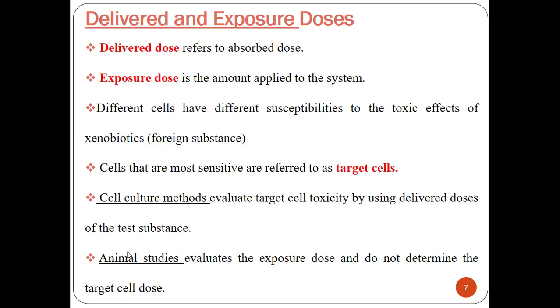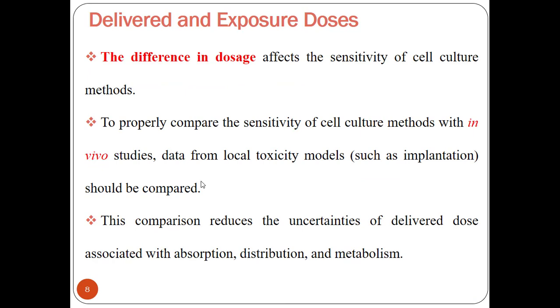Animal studies evaluate the exposure dose and do not determine the target cell dose. In the cell culture method, we have evaluation of the delivered dose, whereas in animal studies, we have evaluation of the exposure dose. The difference in dosage is a key factor in the sensitivity of cell culture methods. There must be a comparison between cell culture methods and in vivo studies. To properly compare sensitivity, data from local toxicity models such as implantation should be compared, as this reduces uncertainties of the delivered dose.